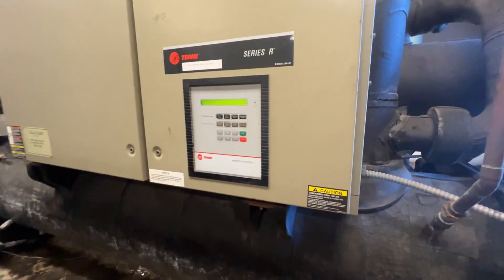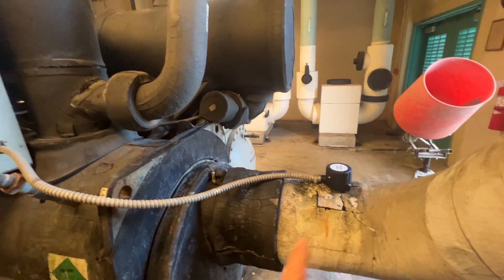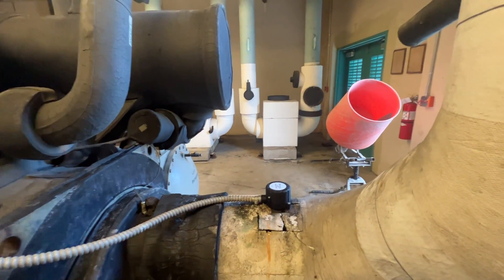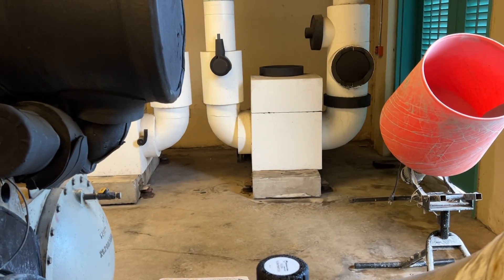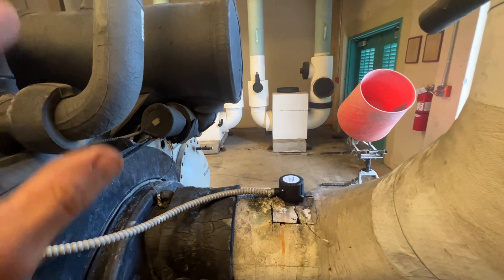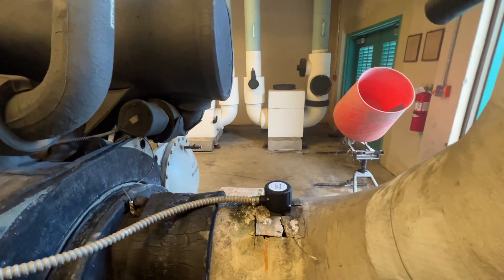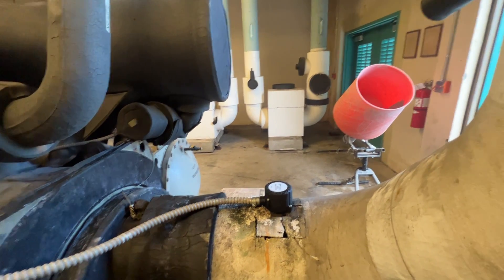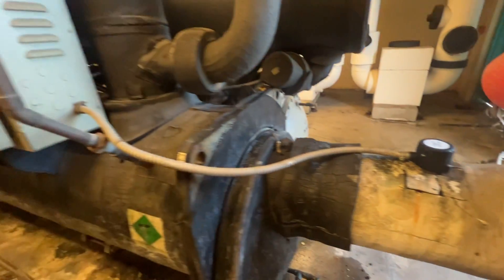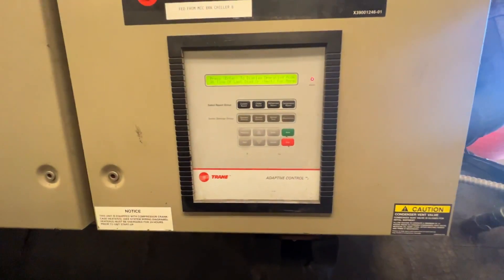I'm looking at this Trane RTHC. I was here yesterday and put a new float switch on it. That primary pump was cavitating and we weren't getting water flow. Some contractors had just installed it and they didn't put any bleed ports on the top of the pump, so it got air trapped in it. I got that bled out and put a new float switch on — it was pretty rusted out. It wasn't starting yesterday because it was waiting for a need to cool.